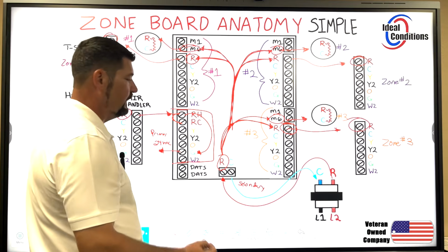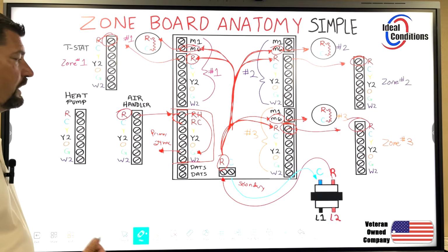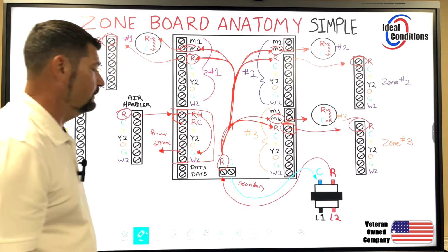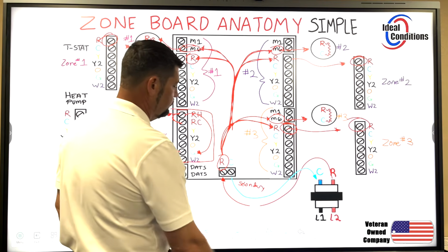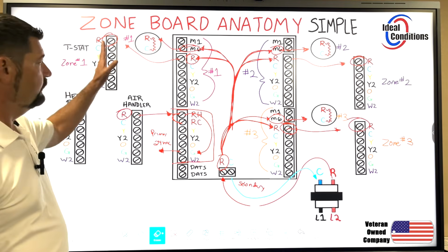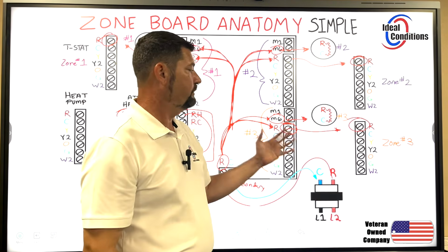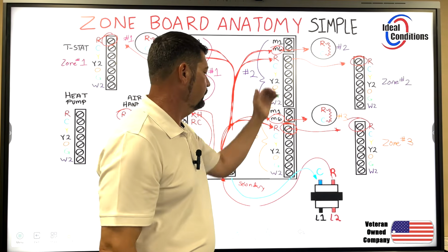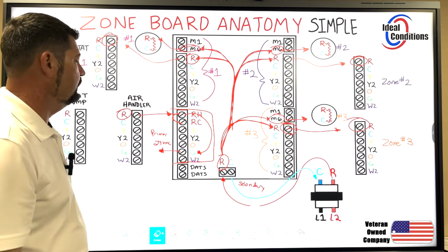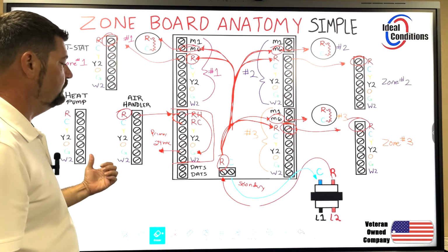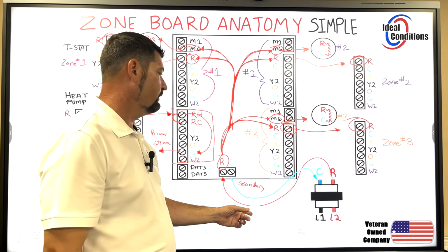this is not something that you would, people ask, hey, well, if I had a float switch, which R would I break? It doesn't matter, because if I put a break here, all right, every one of these thermostats is not going to be able to put power back to these other terminals, and now this zone board can't put power out to the equipment. So I can break here with my float switch.